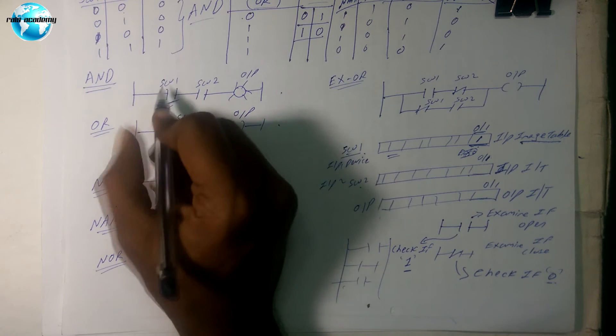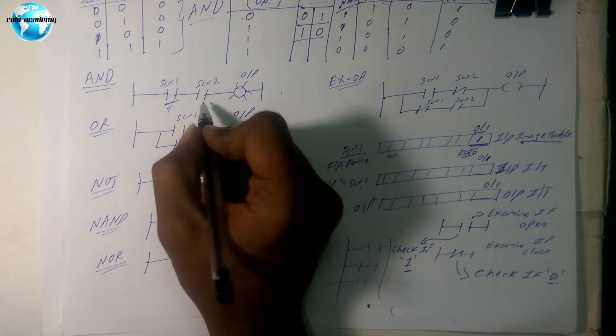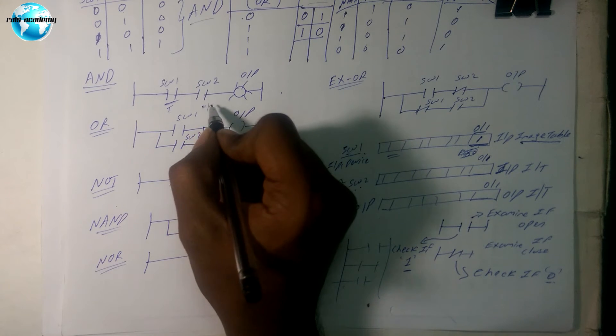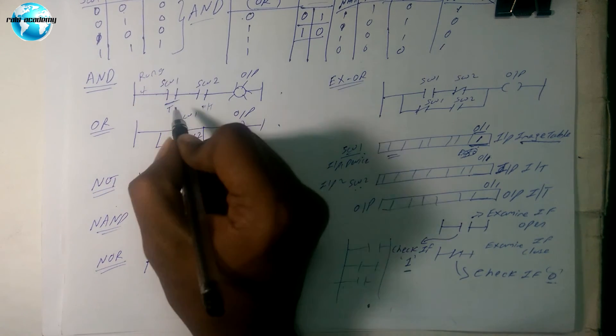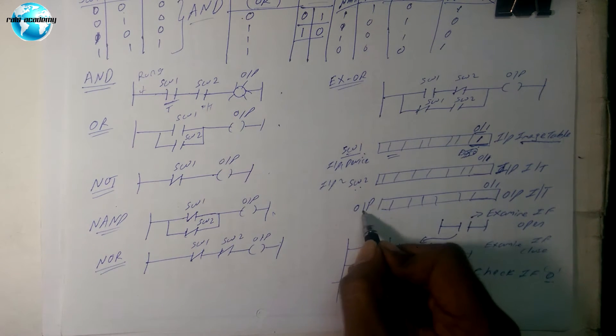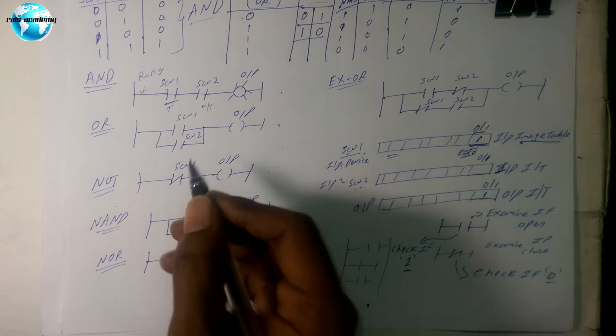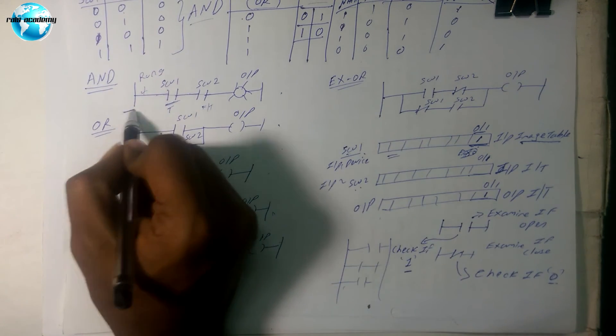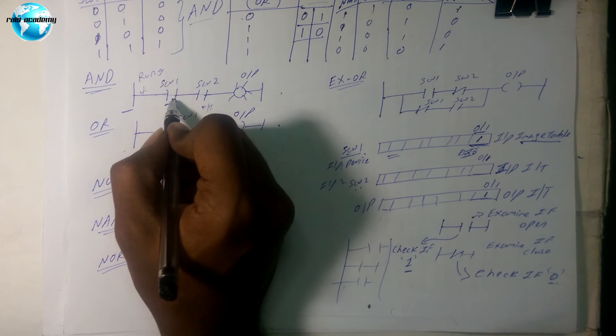If the condition is true — meaning the person has pressed the button — it will give a true indication. On a PC display, the contact will glow green. If the switch is not pressed it shows false; if pressed it shows true. When the rung becomes true, the output coil becomes true, the output image memory is set to one, and the output lamp glows. This is how AND logic works: if the button is not pressed, the bit is zero.